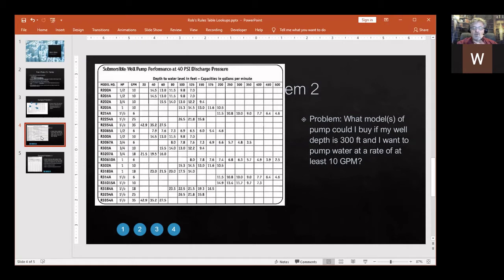When you're picking the right well pump you want to make sure that for the depth of your well, that is how far up your pump needs to pump, you get the water pressure you want in your house. If you oversize it then your pump will be cycling. It'll be pumping really fast, really hard and then stopping, and you'll be wasting energy and it won't be an ideal scenario.